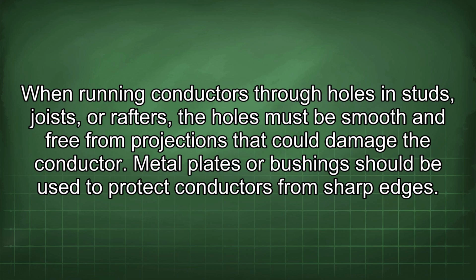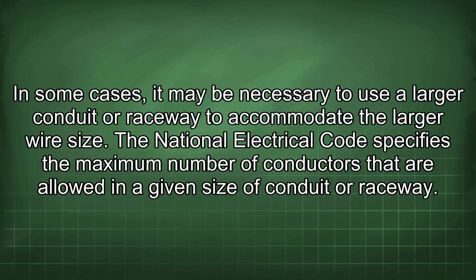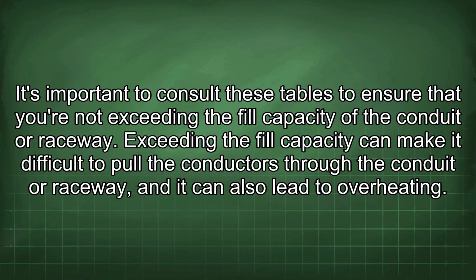Metal plates or bushing should be used to protect conductors from sharp edges. In some cases, it may be necessary to use a larger conduit or raceway to accommodate the larger wire size. The National Electrical Code specifies the maximum number of conductors that are allowed in a given size of conduit or raceway. It's important to consult these tables to ensure that you're not exceeding the fill capacity of the conduit or raceway. Exceeding the fill capacity can make it difficult to pull the conductors through the conduit or raceway, and it can also lead to overheating.